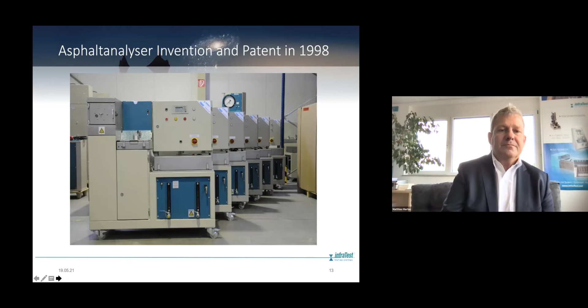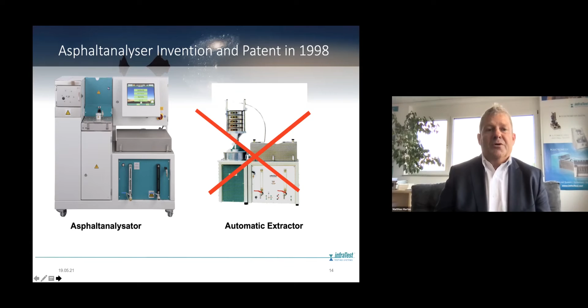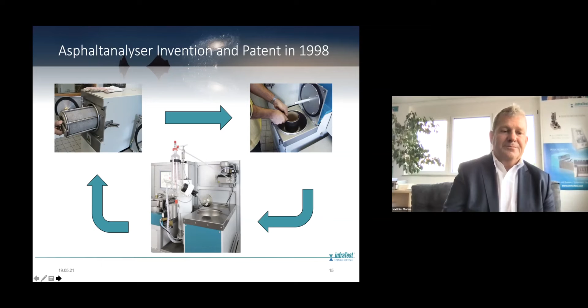Before that, everybody was making, including us, some sort of automatic extractor where you openly had to handle the solvents, which are dangerous. And so we invented this Asphalt Analyzer, where we put everything inside a machine and inside a closed chamber. It starts with the filling of a so-called washing drum. Then you go to the centrifuge, and as you can see here in the circle, then the recovery is coming. And at the end, the binder is automatically recovered with the evaporator.